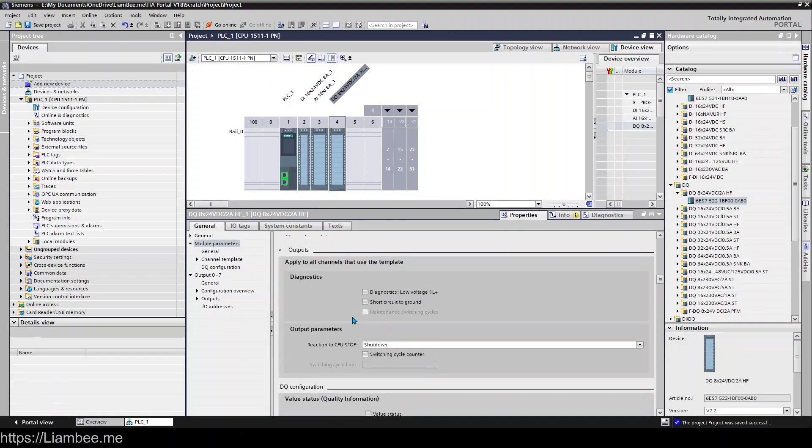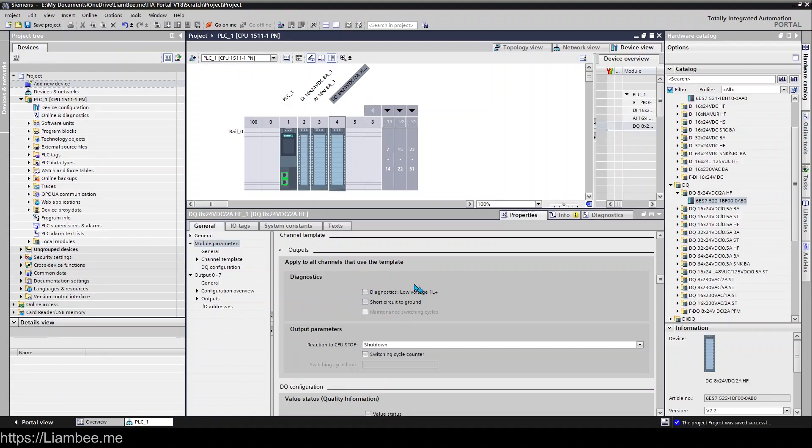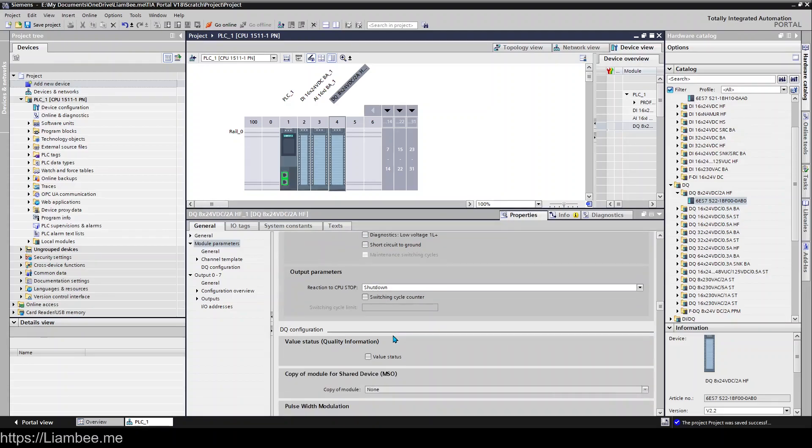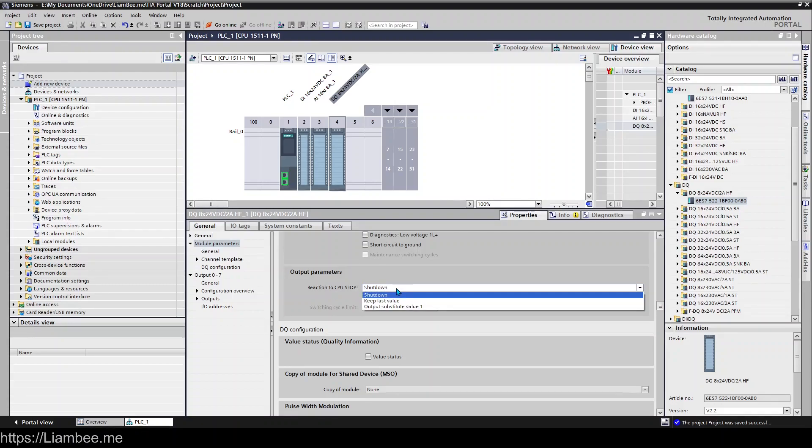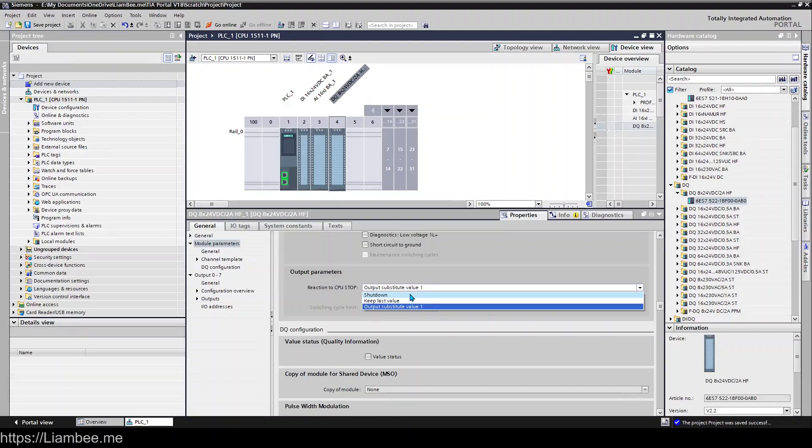So this is things like our output use templates. Apply all channels that use the template. So right now we're not having any diagnostics and we're not detecting a short circuit ground. If a CPU stops, or if the CPU stops, we're set to stop. Then we should shut down, but we can say keep the last known value or substitute the value. If you choose substitute the value to one, then it's going to output true when the CPU is stopped.